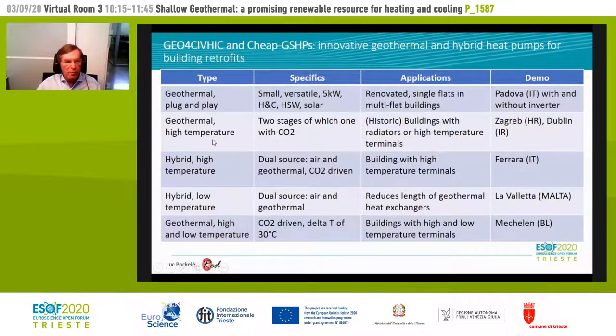We already developed a high temperature heat pump, a 2-stage one, of which 1 stage is with CO2, which is a user-friendly refrigerant with a global warming factor of 1. This was developed for historic buildings where we cannot replace the radiators without destroying them. We tested that in Zagreb, and we are going to test an optimized version in Dublin, where we hope to reach COPs of 3, which is quite good performance for this type of heat pump.